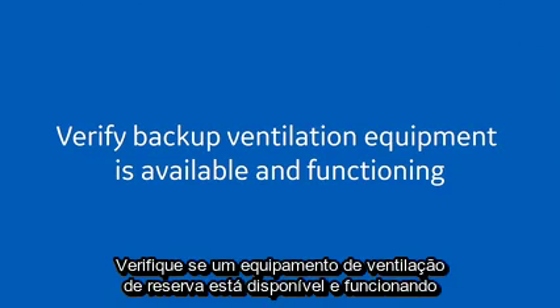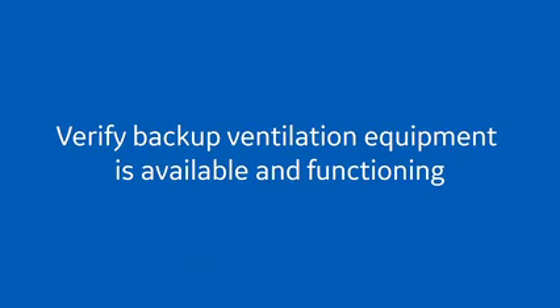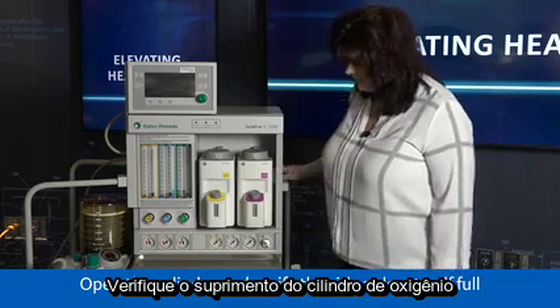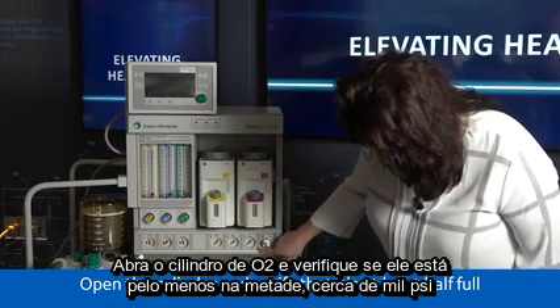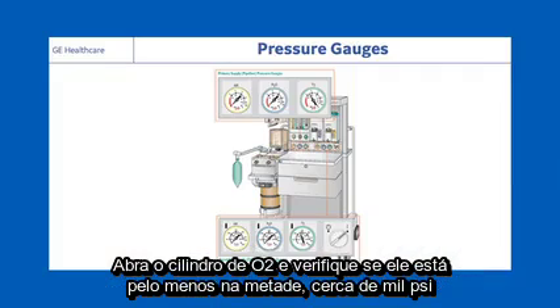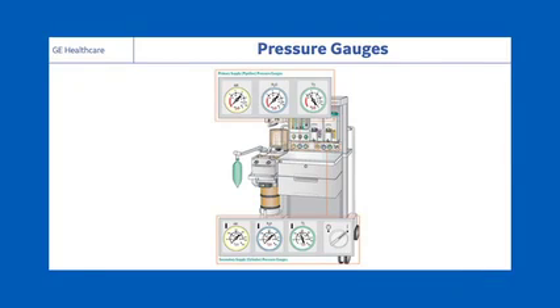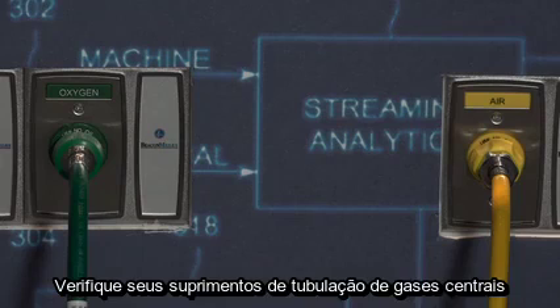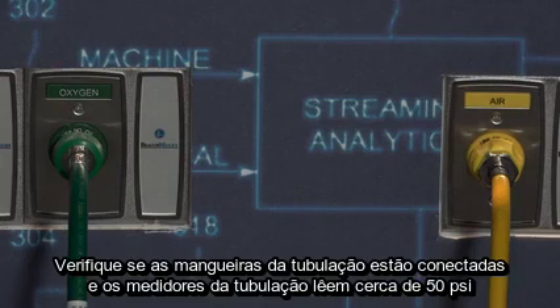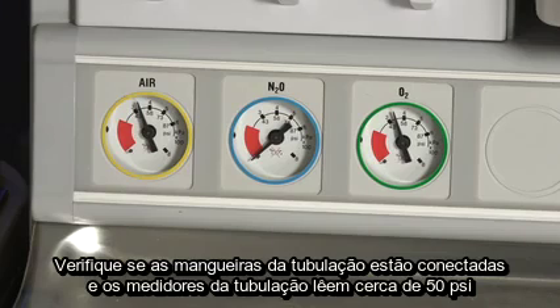Verify backup ventilation equipment is available and functioning. Check oxygen cylinder supply. Open the O2 cylinder and verify that it's at least half full, about 1,000 psi. Close the cylinder. Check your central pipeline supplies. Check that the pipeline hoses are connected and pipeline gauges read about 50 psi.